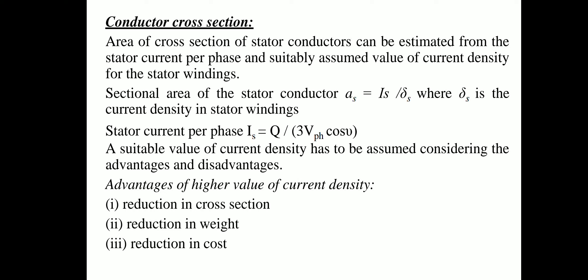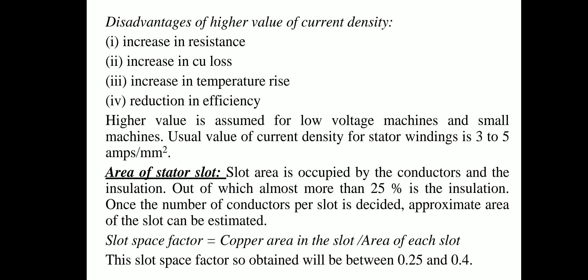A suitable value of current density must be assumed considering advantages and disadvantages. Advantages of higher current density: reduction in cross-section, reduction in weight, reduction in cost. Disadvantages: increase in resistance, increase in copper losses, increase in temperature rise, and reduction in efficiency. Higher values are assumed for low voltage and small machines. The usual value of current density for stator winding is 3 to 5 A/mm².